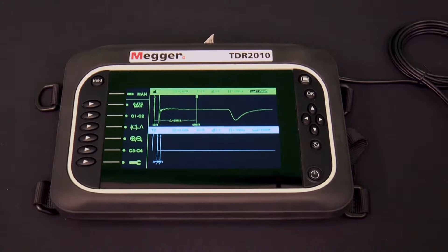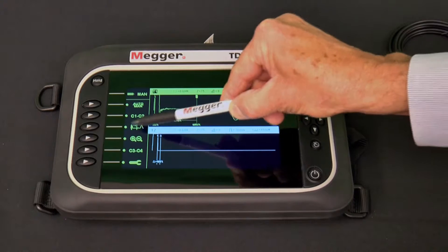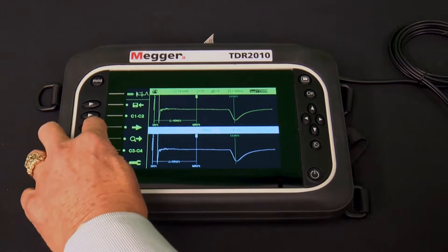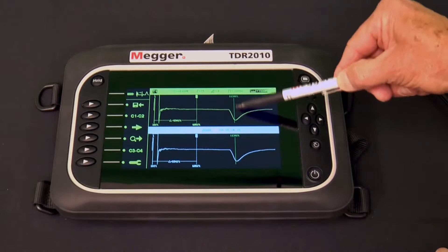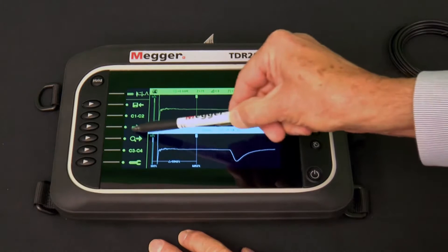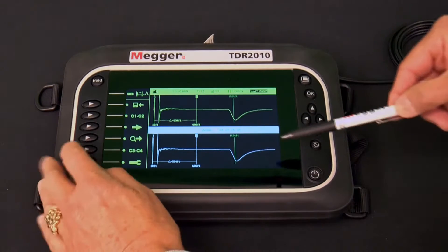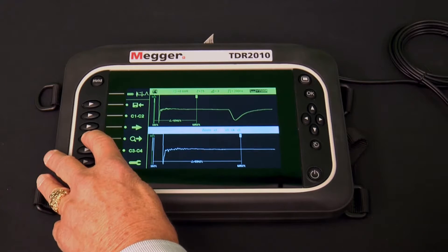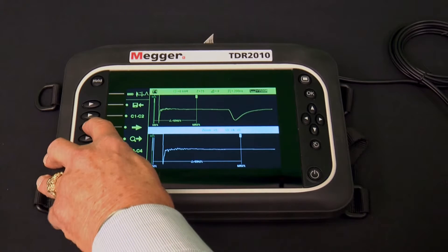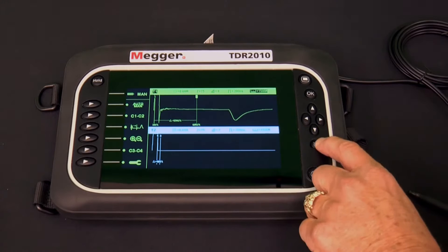Now that we have explored manually locating the event, let's look at the TDR2010's expert function, which makes the TDR2010 find events on the cable under test. The expert soft key is the third from the top — its icon is a trace with a small right-facing arrow. Press this soft key and a new cursor appears where the TDR2010 finds an event. The distance to that event is displayed at the top of that new cursor. The expert icon now changes to a large solid right-pointing arrow, and the inactive trace is replaced with a zoom trace of the active trace. Additional presses of the expert soft key will cause this cursor to move to additional events further along the cable under test. Press the back key to exit the expert function. That covers the basic analysis operation of the TDR2010.